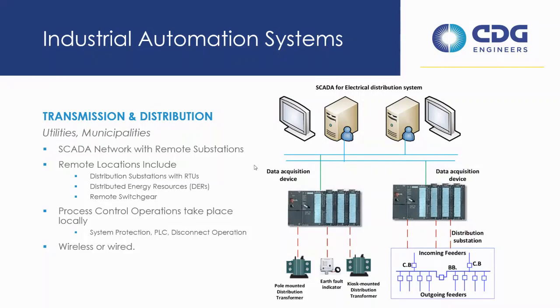transformers, downstream transformers, that stuff typically does not communicate back to a central automation system. It's just there to protect. But you can put it in a remote terminal unit, an RTU, and communicate that stuff via SCADA if it's fiber or remote or wireless type communication back to your central hub. So that way you can know what's going on out in your field. If your breakers opened up, if your reclosers operated, if something's tripped, a long time trip sitting, it's been overloaded or that sort of thing.